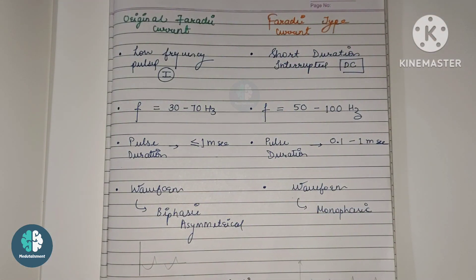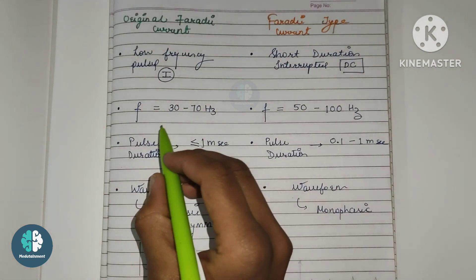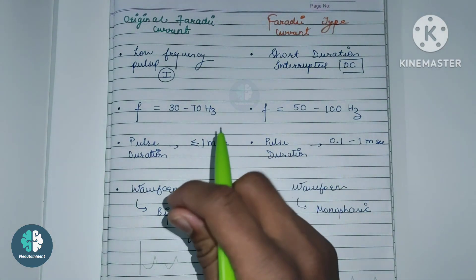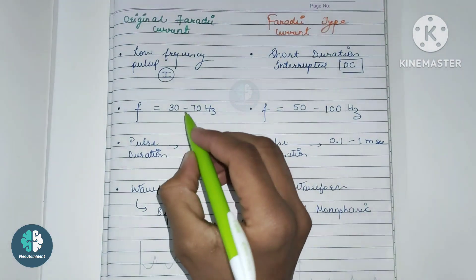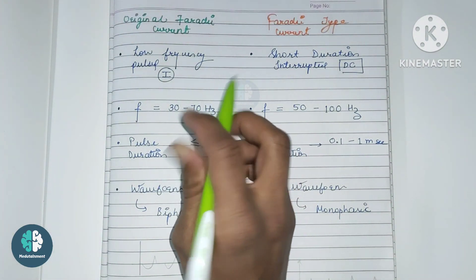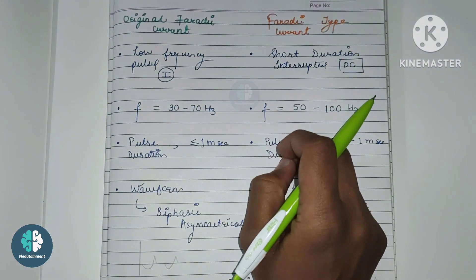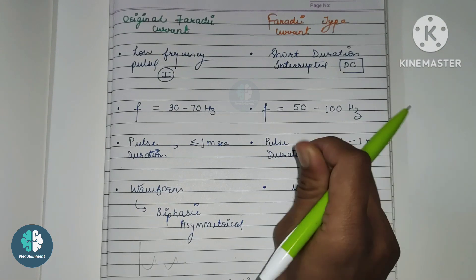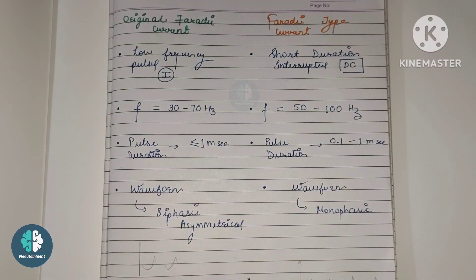Next is frequency. The original faradaic current has a frequency of about 30 to 70 hertz, whereas the faradaic type current is about 50 to 100 hertz. Both differ slightly — the original has a lower frequency range while the faradaic type has a wider frequency range.